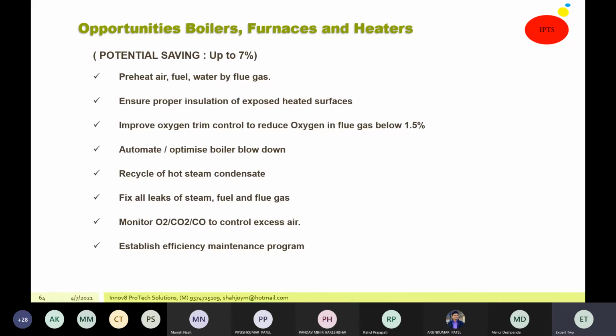Recycle hot steam condensate. Fix all leaks of steam, fuel and flue gases. Monitor oxygen, CO2 and CO to control the excess air. And ultimately you have to establish an energy efficiency maintenance program so that you identify the efficiency loss early and take the corrective action.